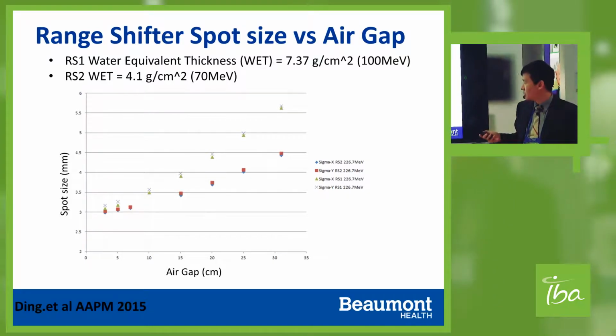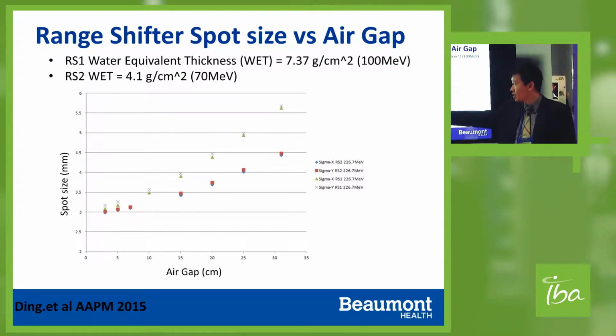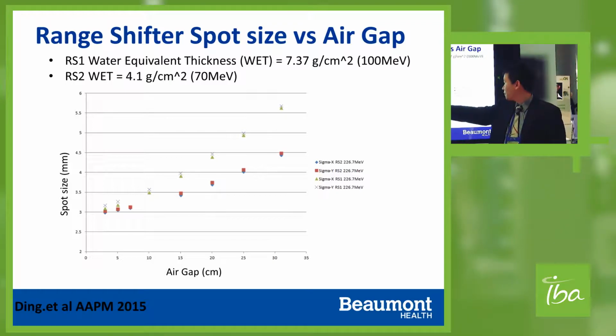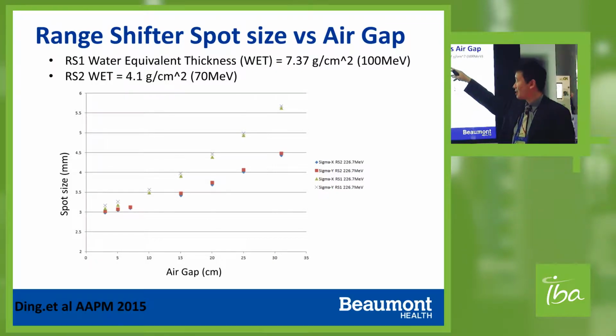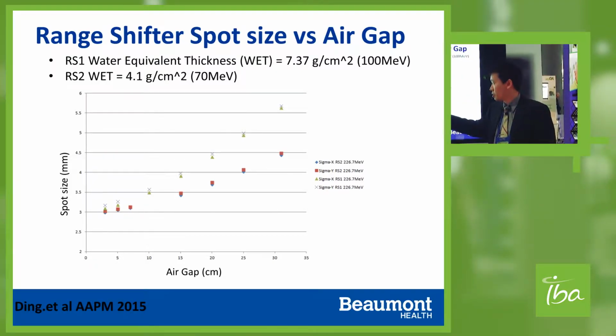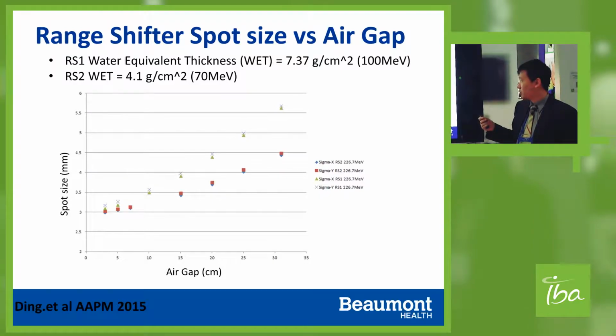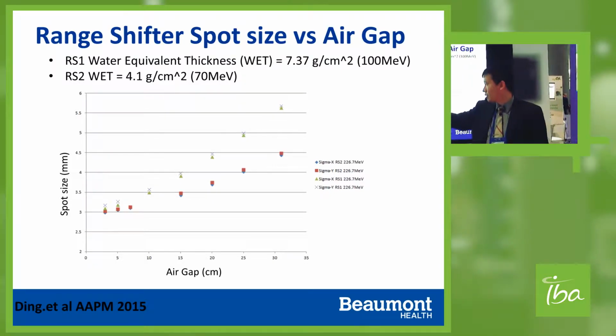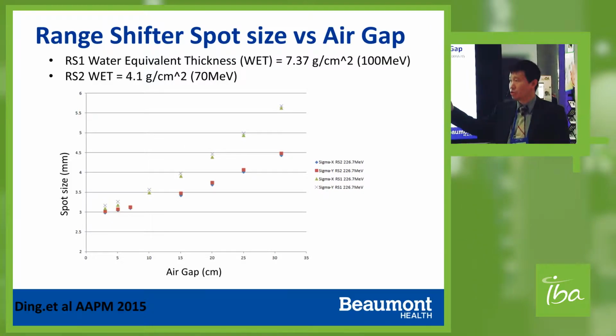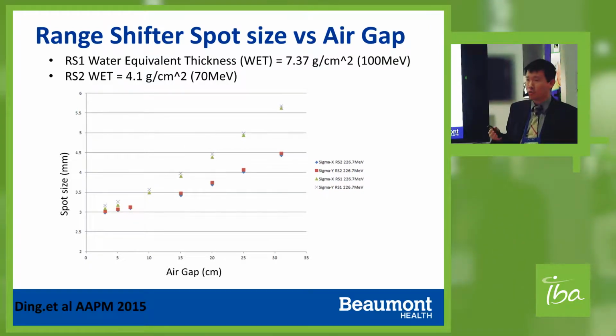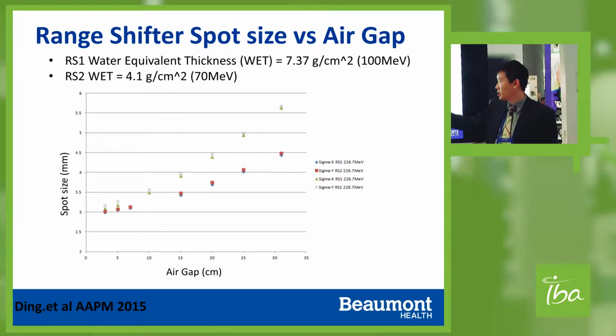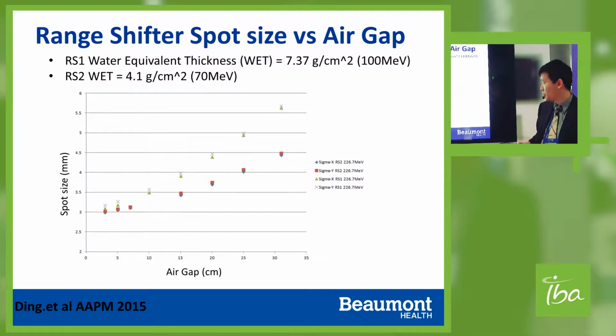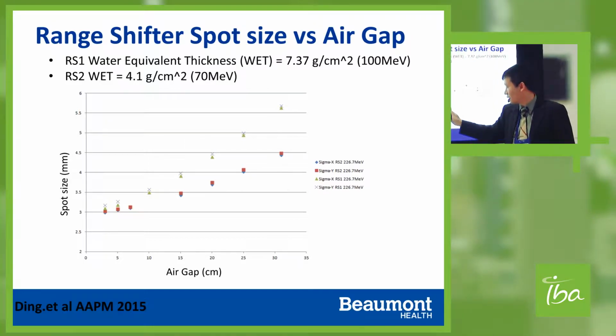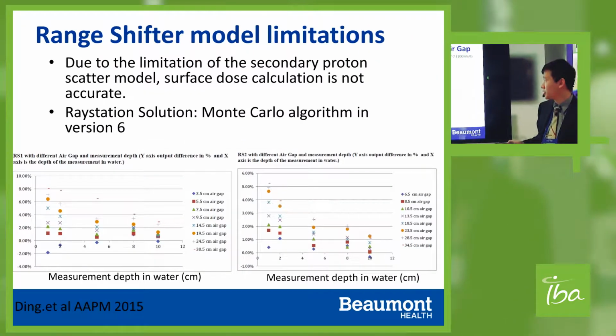So this is a spot size plot from different air gaps. As you see, with a different range shifter at different air gaps, the spot size increased a lot because of the scatter in the air. So the good part is when you minimize the air gap, you have a better modulation, which means you have a better treatment quality for your brain and head and neck patients. While if you increase the spot size, you will lose this modulation capability. So that's why we need to keep the air gap as small as 15 cm or less for practical purposes.